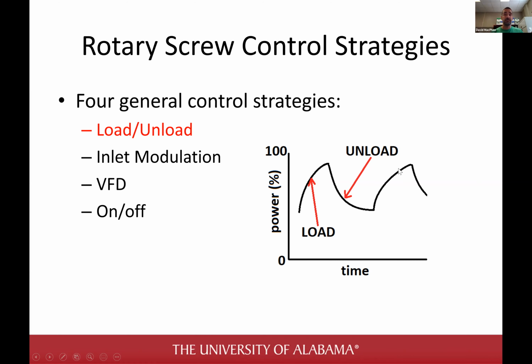So you have a load fraction and an unload fraction. Why don't they just shut it off? You might ask. Well, that's option number four: on-off control. That's really bad for motors. If you know something about motors, you know you're not supposed to turn them on and off a lot, because it heats up the copper windings to the point where repeated cycling can cause overheating, melting, and you'll be looking for a new compressor.